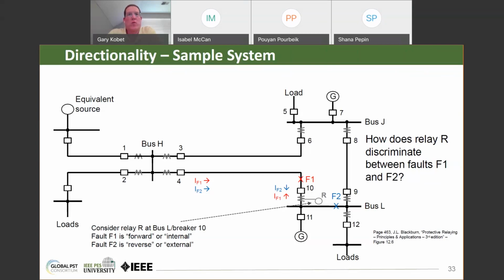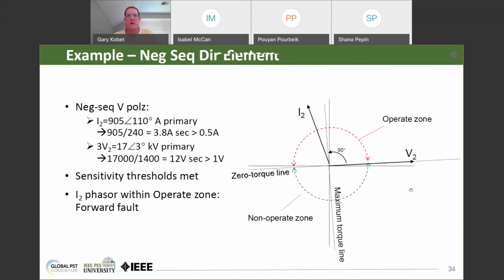Next slide, please. One way that this is done is with a negative sequence comparison. I said this a second ago, but this is just to illustrate. The V2 is the polarizing quantity, and the I2 is the operating quantity. And when I2 leads V2 by 90 degrees, or plus or minus 90 degrees either side of that, then the negative sequence element can make a decision.